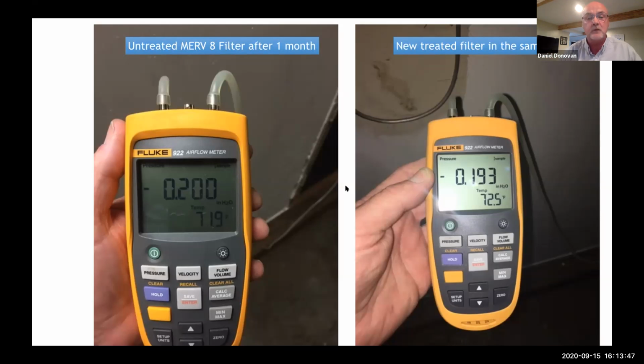This is a smaller unit, 8,000 CFM, and it only has 8 filters. But this one here on the left was the MERV 8 filters after a month. They were due their monthly change the day that we actually changed out with the treated MERV 8 filter. And this was the filter after a month, exactly 0.2. And when we put in the treated filter, it was 0.193. And this really is not apples to apples, because we don't know, maybe this was less when it was new, so there was an increase. But that was to give me an idea of what was happening. But when we actually did the main air handler, there was zero increase in static across it with the treated filter.